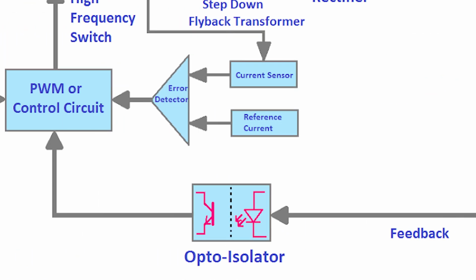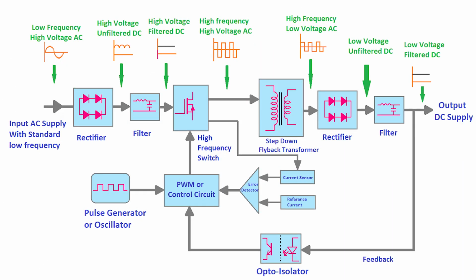The protection circuit gives feedback to the high voltage part on the oscillator, either to shut down the passage of voltage to the transformer when there is overload or overheating. Failure of the feedback circuit may lead to component damage, and that is what happened to this SMPS.